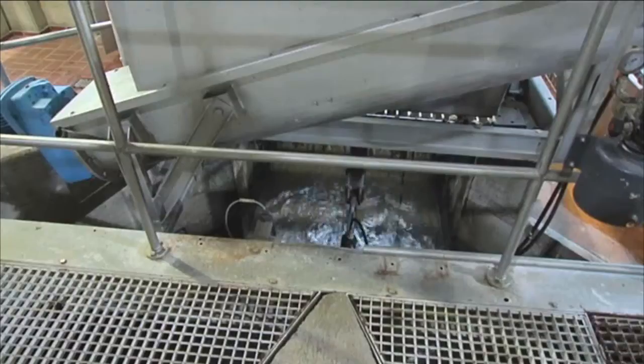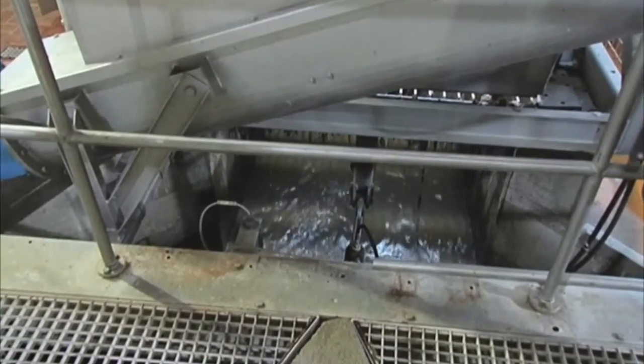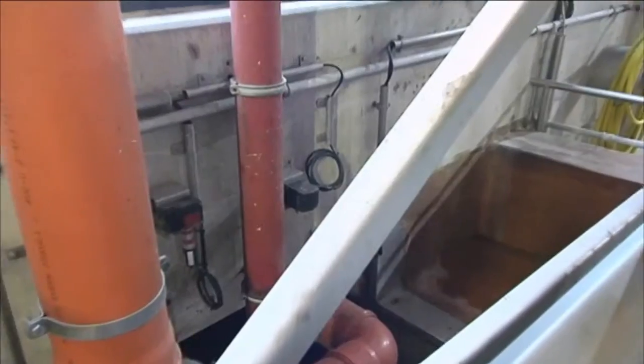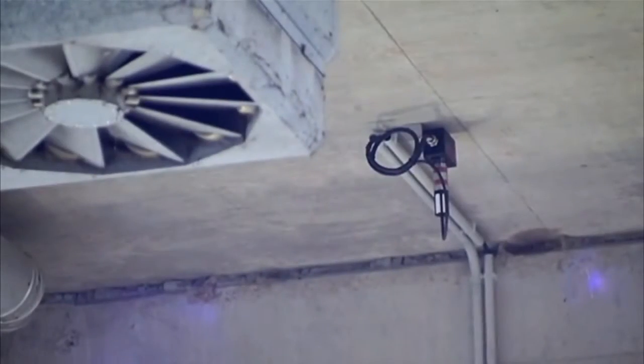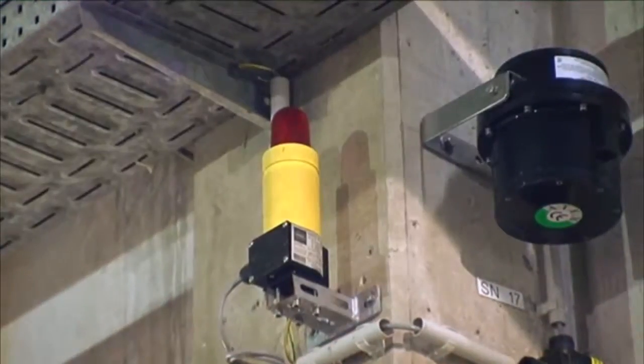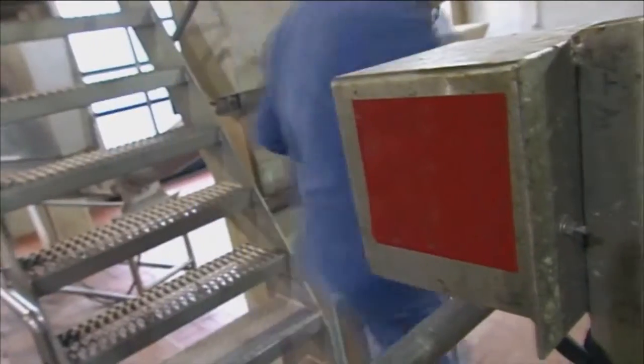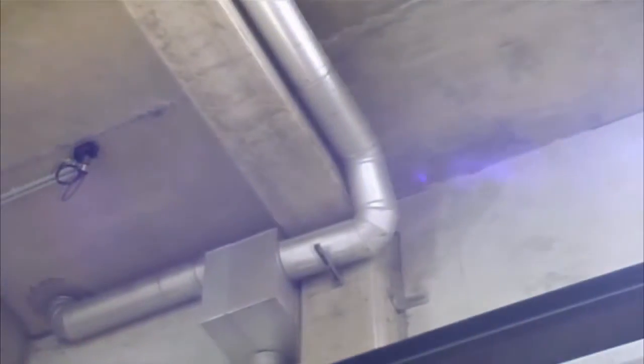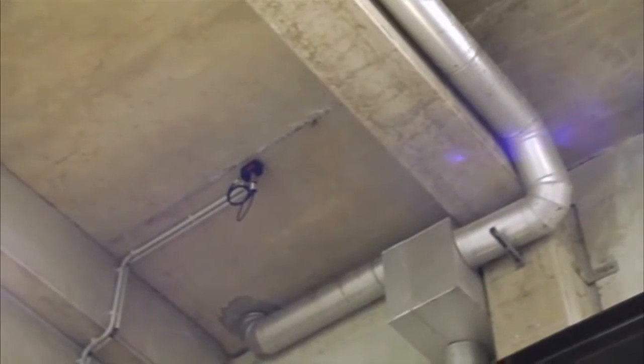For example, when the wastewater is contaminated with solvents, and there is a hazardous concentration of combustible gases in the racking hall, in a matter of seconds, the gas concentration is identified. Personnel in the affected area are warned immediately, and the doors open automatically. The gas concentration is diluted by the influx of air, thus ensuring that an explosive mixture does not form.